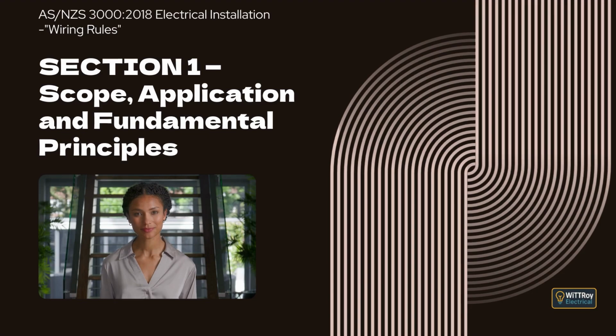Clause 1.4.32 is Class 2 equipment. This is equipment where protection from electric shock does not rely only on basic insulation, but includes extra measures such as double insulation or reinforced insulation. There is no need for earthing or installation conditions to provide the protection. Class 2 equipment may include equipment made with durable, continuous insulation that surrounds all metal parts, except for small parts such as screws or nameplates. Or equipment made with a continuous metal enclosure where double insulation is used throughout, except for parts where double insulation cannot be practically done. There are also types that combine these two methods.